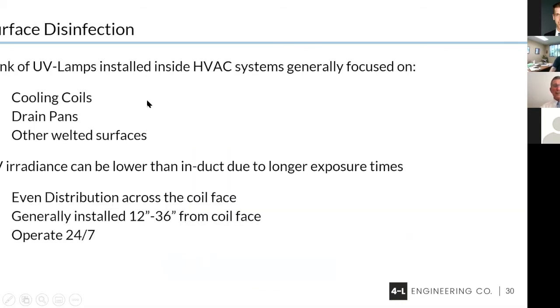We can put this UV lighting on the wet side of a cooling coil. It will help control the buildup in the drain pans or any wetted surfaces. You have to set the light so that it evenly shines on the entire face area of the coil. It normally needs to be set back off the face of the coil somewhere around 12 to 36 inches, and you operate it 24/7, or 24 hours a day, 7 days a week.